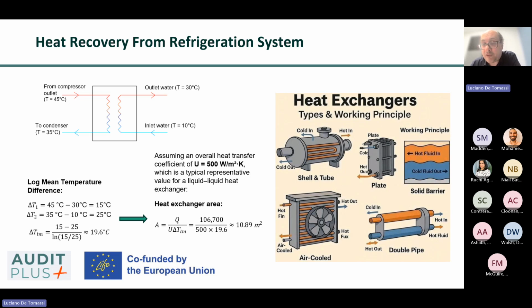The sizing of any heat exchanger for refrigeration heat recovery is fundamentally based on the heat duty and log mean temperature difference method. The heat duty is determined from the available condenser heat rejection, which is linked to the refrigeration system's cooling load and COP. Once the required heat transfer rate is known, the heat exchanger size is calculated using the equation Q equals U times A times LMTD, where Q is the heat transfer rate, U is the overall heat transfer coefficient, A is the heat transfer surface area, and LMTD is the logarithmic mean temperature difference between hot and cold streams.